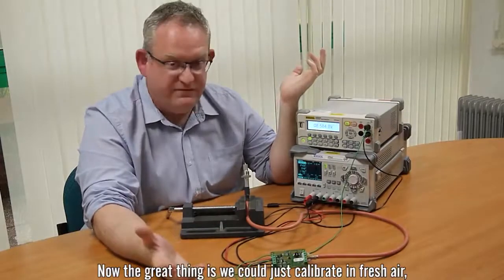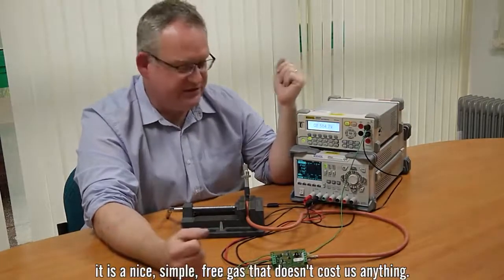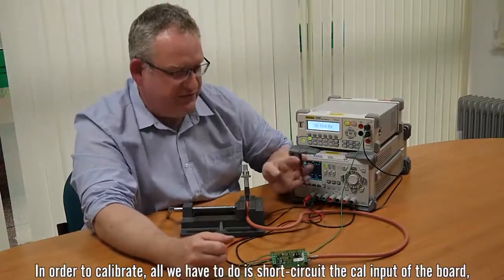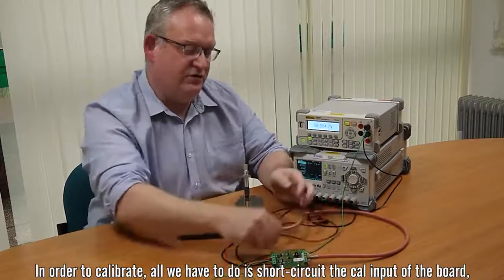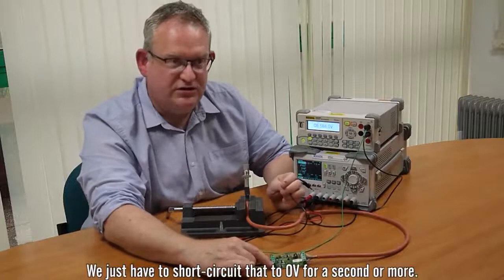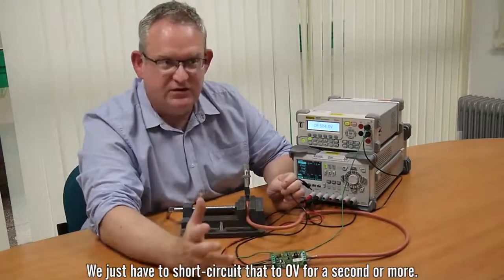Now the great thing is we could just calibrate in fresh air. It's a nice simple free gas that doesn't cost us anything and in order to calibrate all we have to do is short circuit the cal input on the board which is this one here on the end, we just have to short circuit that to zero volts for a second or more.